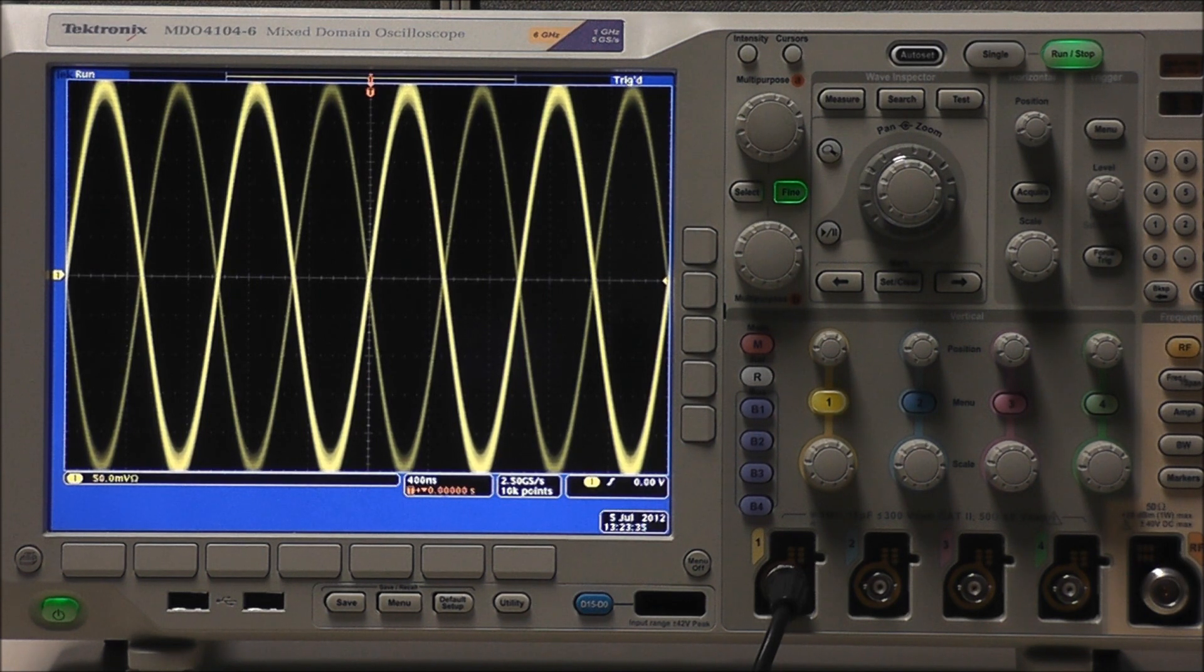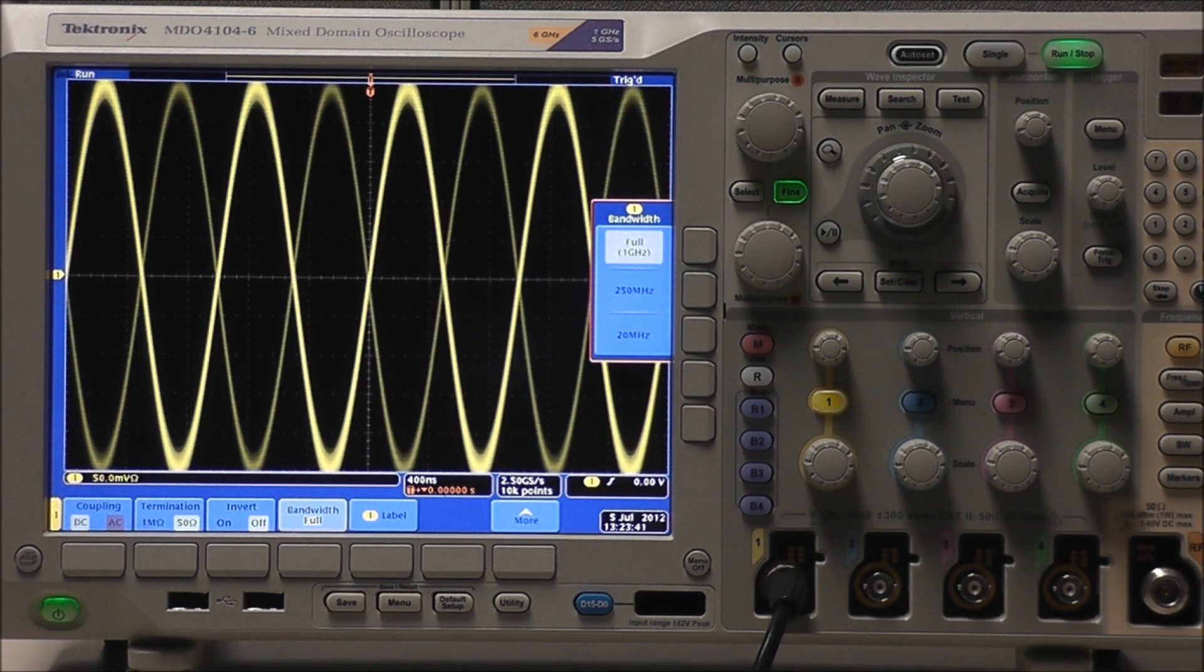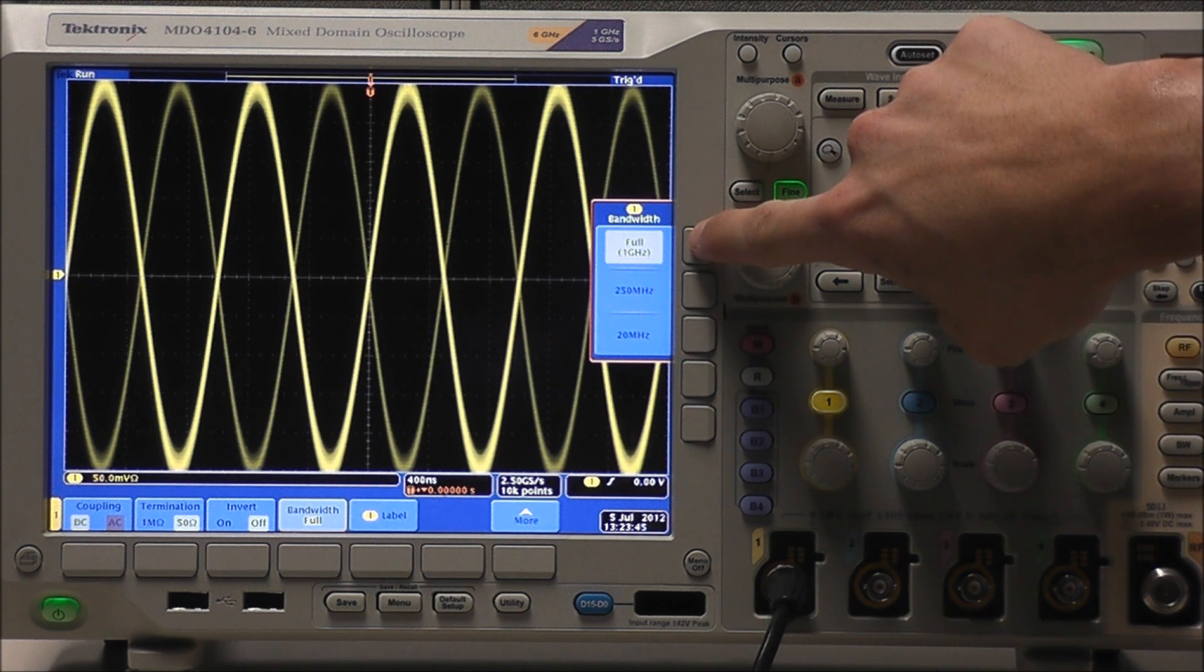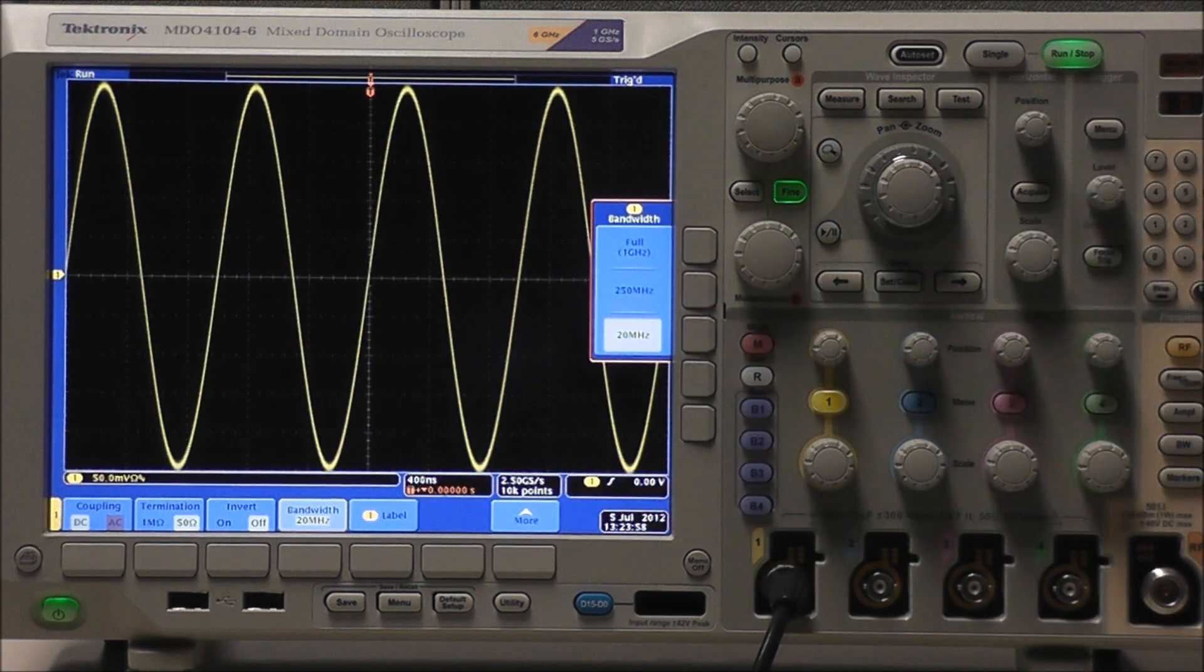We can reduce the input bandwidth limit which acts as an analog low-pass filter. Select channel 1 followed by bandwidth and we have three options to choose from: full or 1 gigahertz which we are currently running. Now obviously the machine is going to read every signal with a frequency less than 1 gigahertz. 250 megahertz and we can see a subtle noise reduction there. But if we select 20 megahertz we can see a very substantial noise reduction.